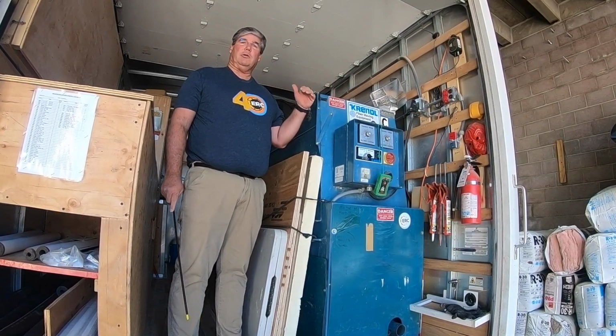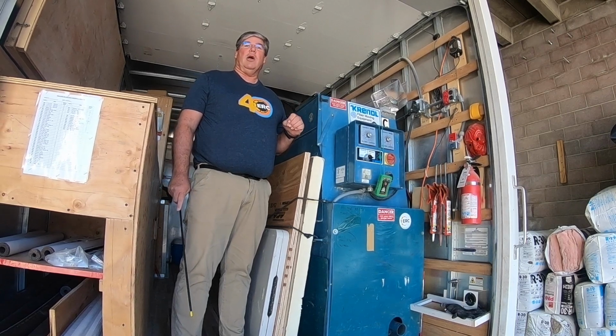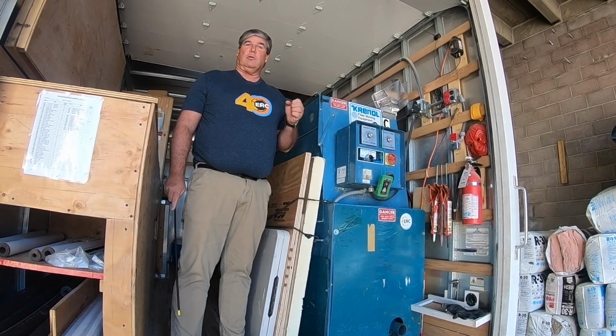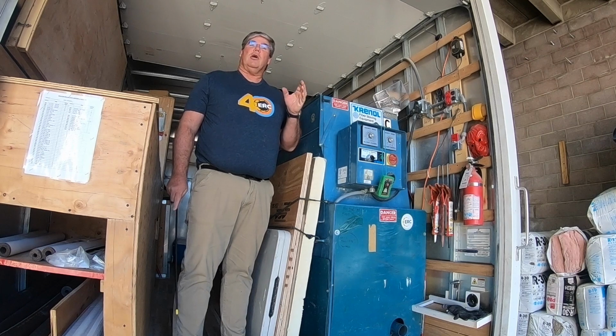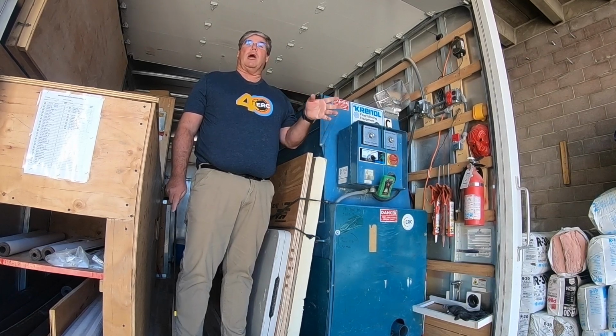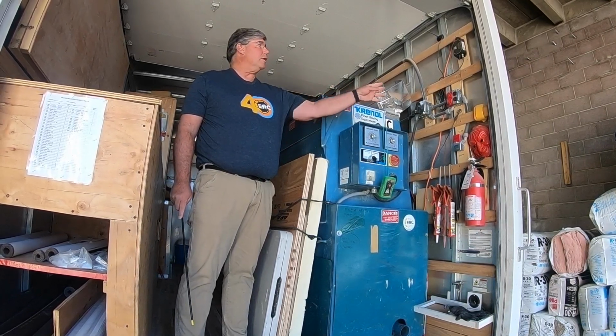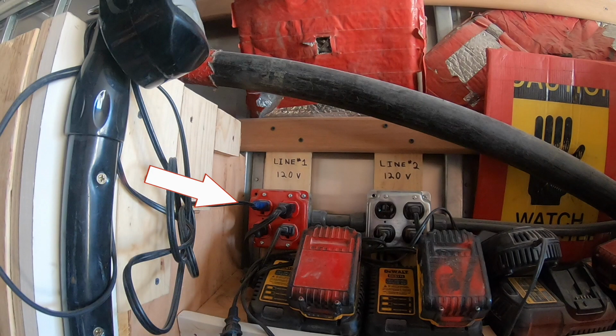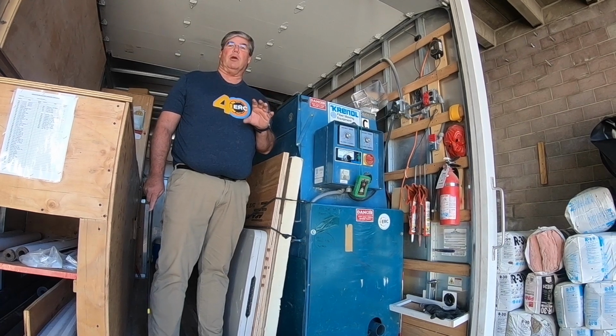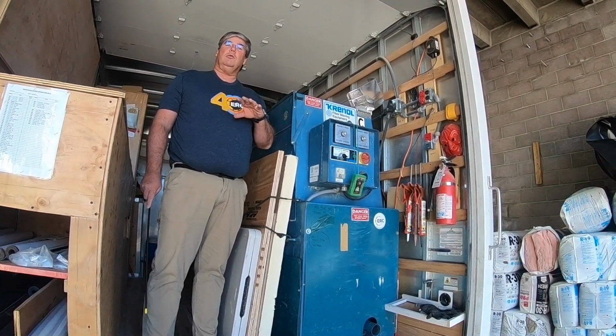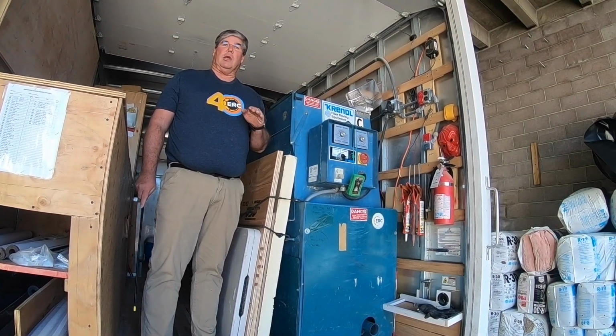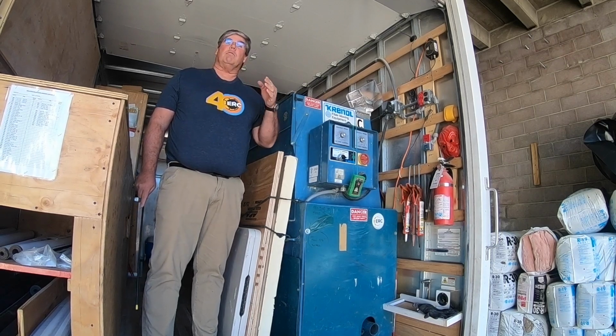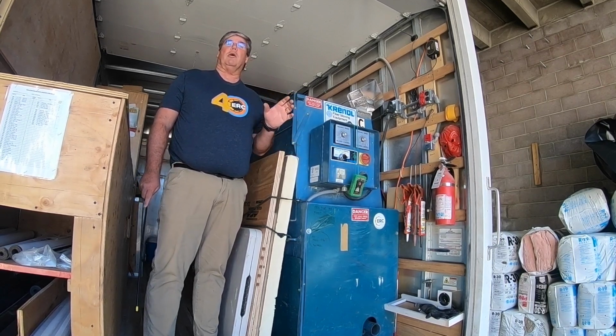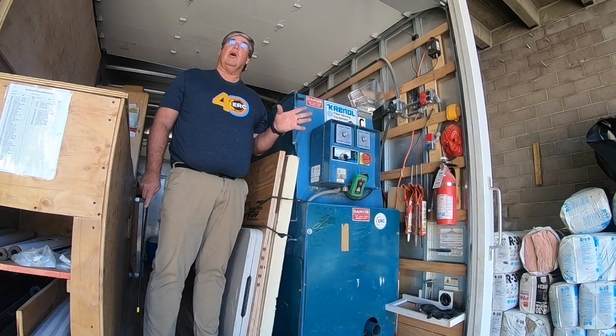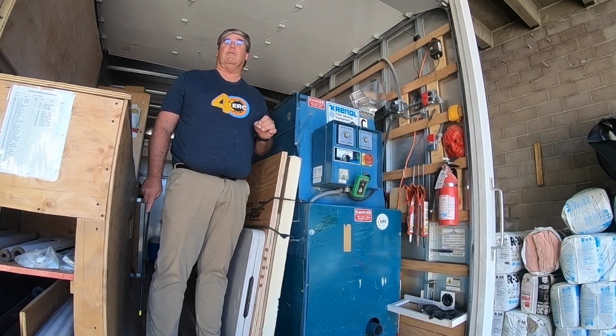On this truck, because it has a single generator, like a diesel or the old Generacs, the bottom line is you still have line 1 and line 2. So the red is line 1, the black or silver is line 2, keeping an even load on the generator. If it's a truck with 2 gasoline generators, I do the same thing so the driver's side and passenger side generators put out about the same amount of electricity. They're supposed to be balanced within 10% of each other.